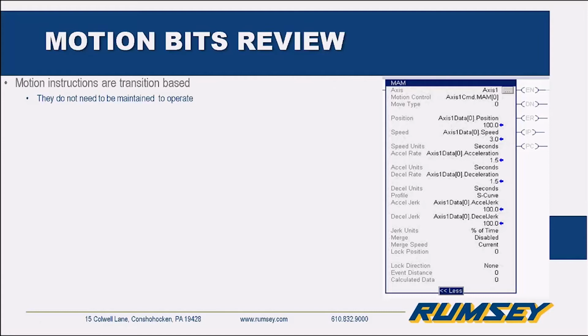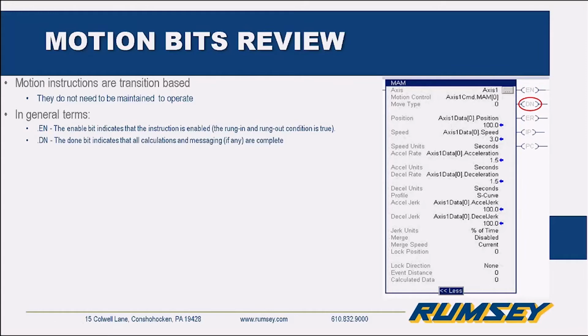It's just reiterating the same thing. They do not need to be maintained to operate. So, for instance, with an MSO, you do not have to maintain that instruction to keep your servo enabled and holding torque. In general terms, for typical instructions, I'm using MAM because quite honestly, it's probably the most common instruction other than turning a servo on and off or resetting it. You have an enable bit. The enable bit is just a mirror image of the rung preceding the instruction. So if the rung preceding the instruction is true, the enable bit goes true. Plain and simple. The done bit, so there are some misconceptions.